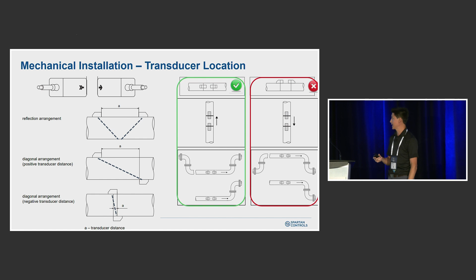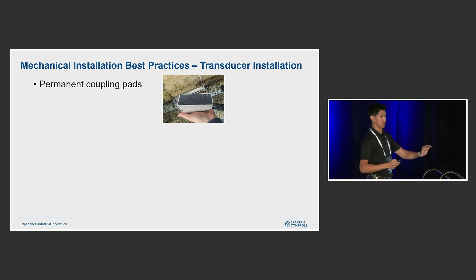Okay, so a couple of things around mechanical installation. For those of you who are familiar with non-contacting clamp-on ultrasonics, typically you'll apply a gel to the pipe and then stick the transducer on. But over time, the gel can evaporate, wash away, whatever. So on our permanent transducers, what we do is we apply a coupling pad. And then we have an algorithm built in that can compensate for the coupling pad, so we don't get a loss in accuracy there. And that way, there's very little to no maintenance on the transducers. You can stick them on, and they're on for good.